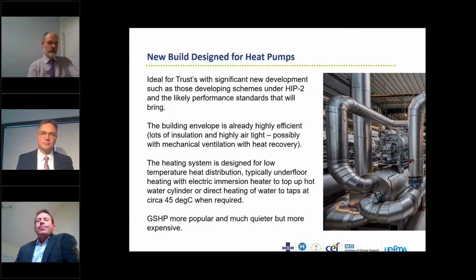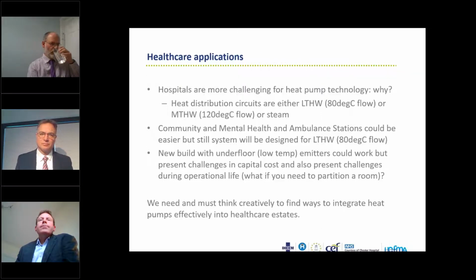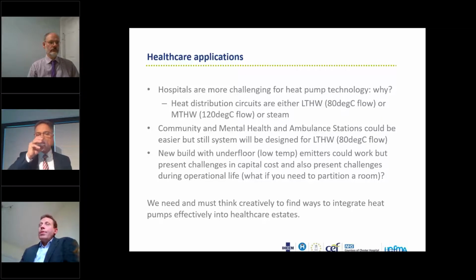Next slide, please. Looking specifically at healthcare applications, hospitals are more challenging for heat pump technology. Why? Because hospitals, particularly acute hospital sites, have been designed with low temperature hot water networks which run at 80 degrees or medium temperature at 120, or there are still quite a lot of sites which still operate on steam. So integrating low temperature heat pump technology is challenging.